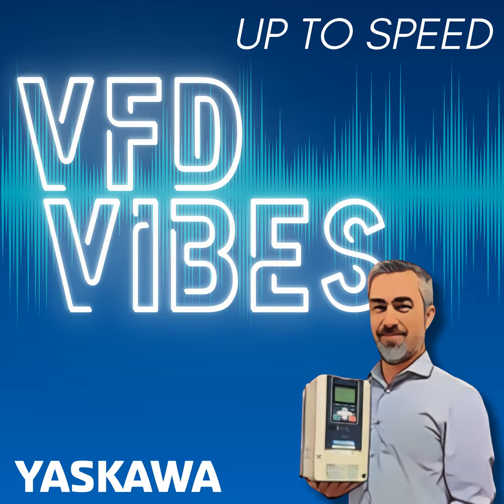And system grounding, which we talked about before, is some part of the power system that is feeding the drive that has to be grounded. This is most commonly the neutral. As we discussed in the previous podcast, most 480-volt industrial three-phase systems are connected as a Y configuration with that neutral solidly connected to ground. Okay, and that ground is called system grounding. And yes, eventually the system ground finds its way to the protective ground. It's all the same thing.